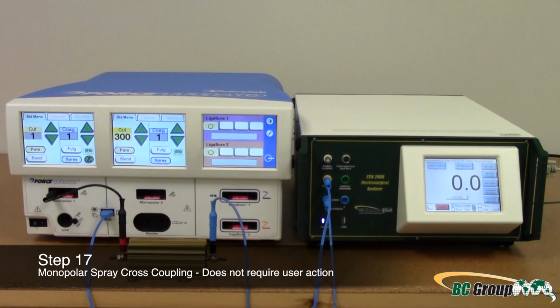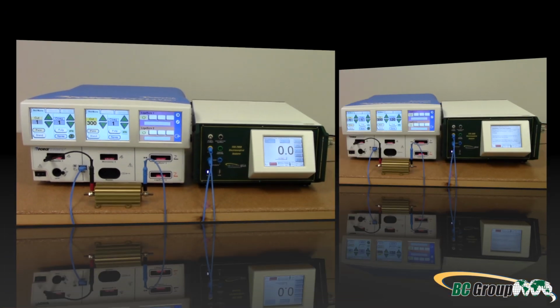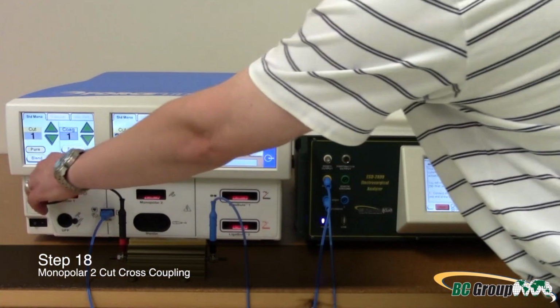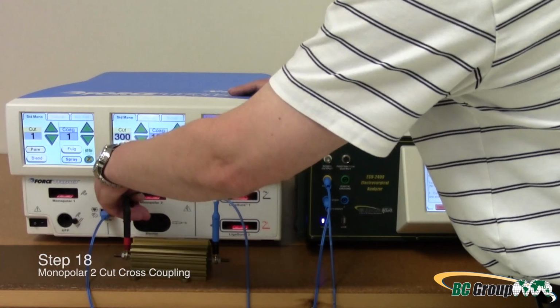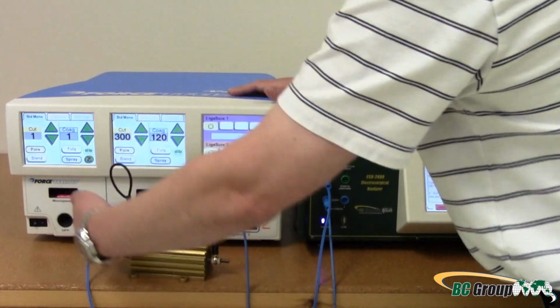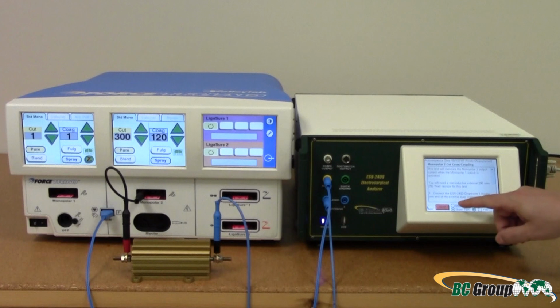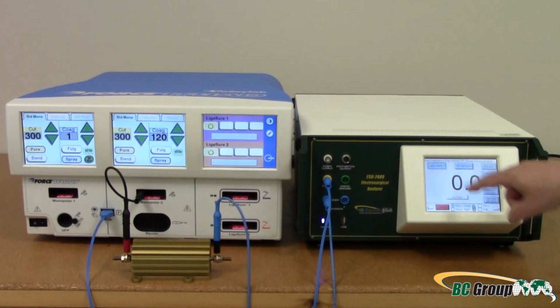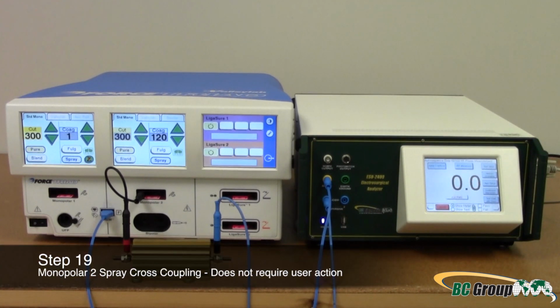Step 17 does not require user action. Step 18. Monopolar 2, cut, cross-coupling. Move the short jumper lead from monopolar 1 to monopolar 2. Select Show Meter and then press Capture. Step 19 does not require user action.